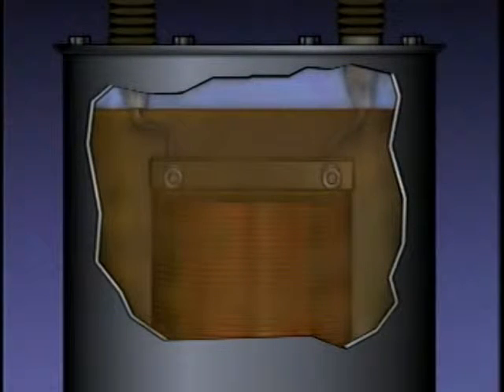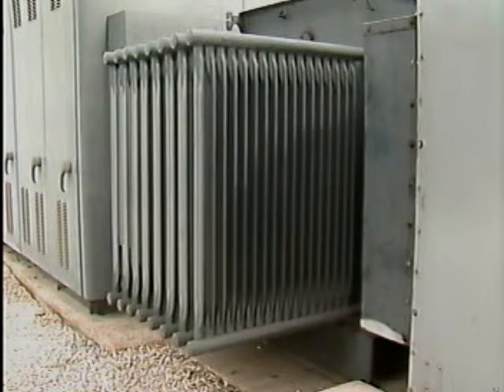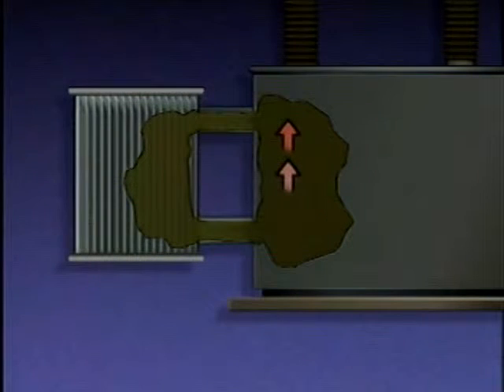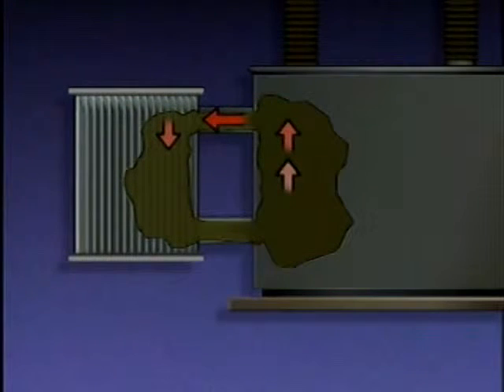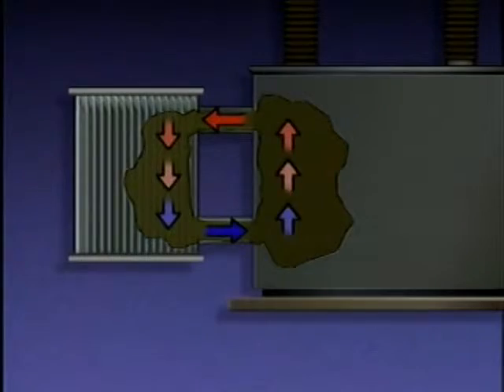Besides insulating the windings, the oil also cools them, which can produce a lot of heat during normal operation. Some oil-cooled transformers have radiators to make the cooling process more efficient. In the arrangement illustrated here, there's a natural circulation of oil. As the oil picks up heat from the windings, its density decreases, causing it to rise. The warmer oil enters the top of the radiators, where its heat is transferred through the radiators to the surrounding air. As a result, the oil becomes cooler and more dense, sinks to the bottom of the radiators, then re-enters the transformer where it can pick up more heat from the windings.